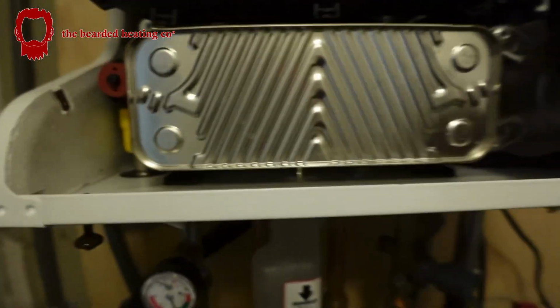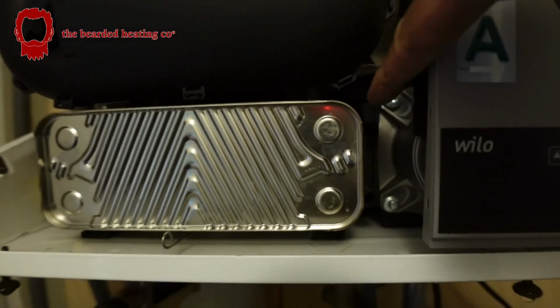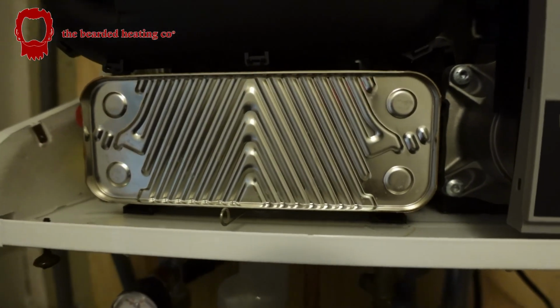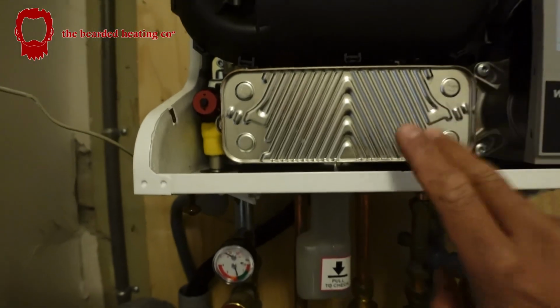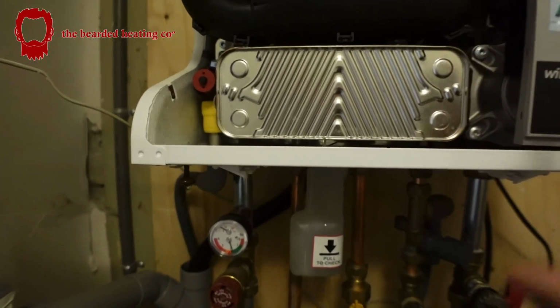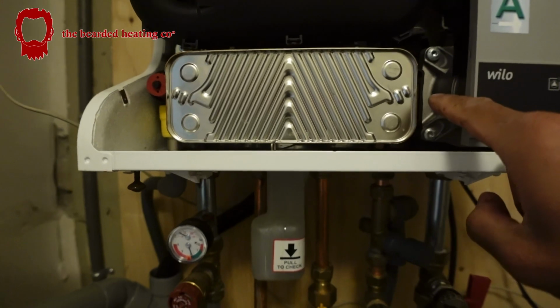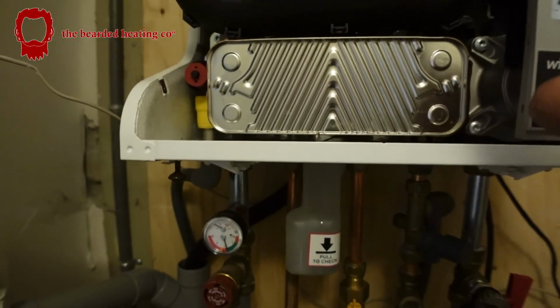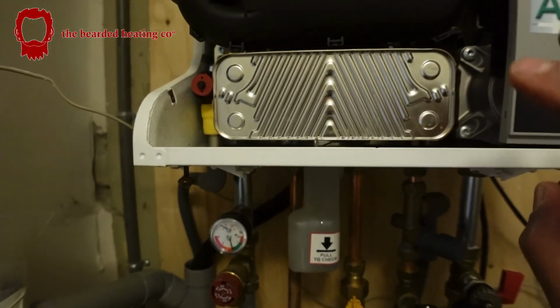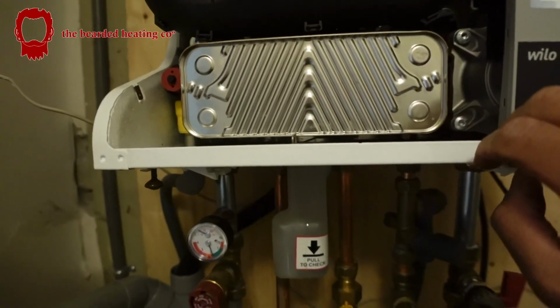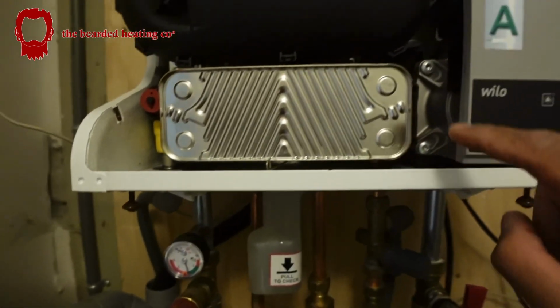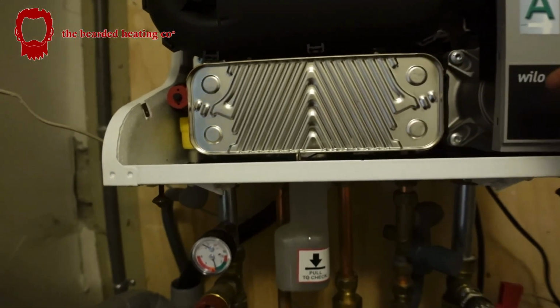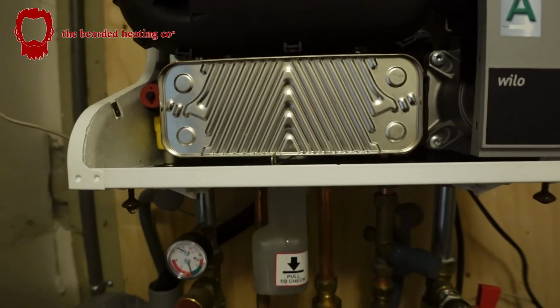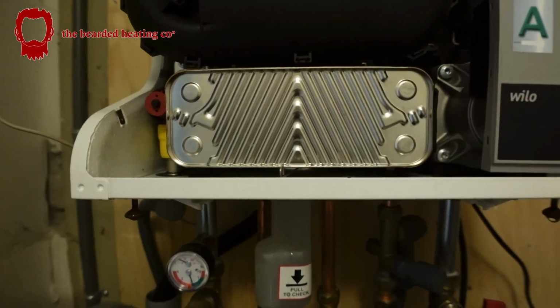The reason it's leaking is because this hydro block has a crack on the cold water inlet. So what I did yesterday was confirm my theory that it was the hydro block leaking. I drained the system down, turned the water off, took the plate heat exchanger off, put new rubber washers on the four washers, put it all back together, and it still dripped, confirming the hydro block is leaking. You can't just get the right hand side, you have to get the whole thing.